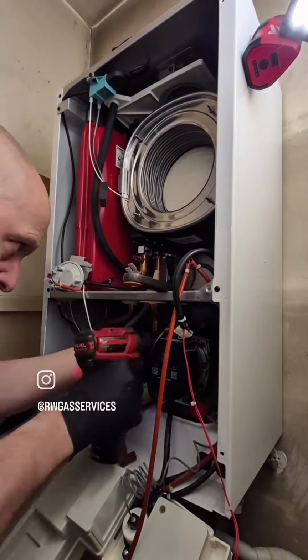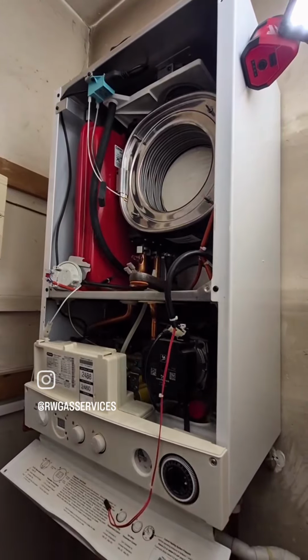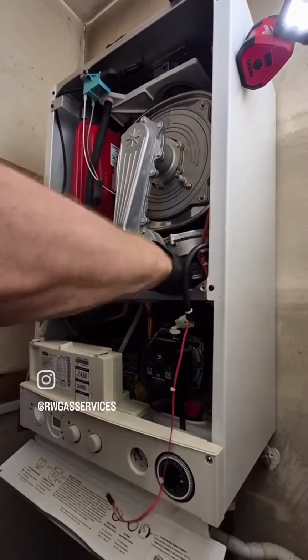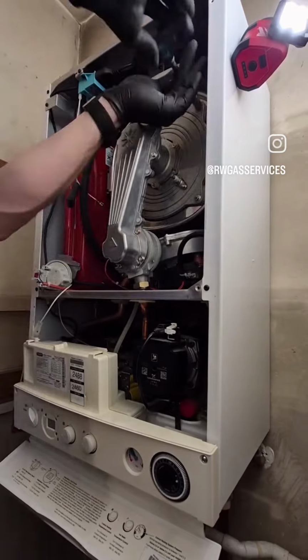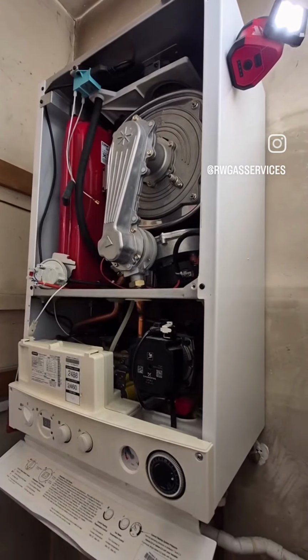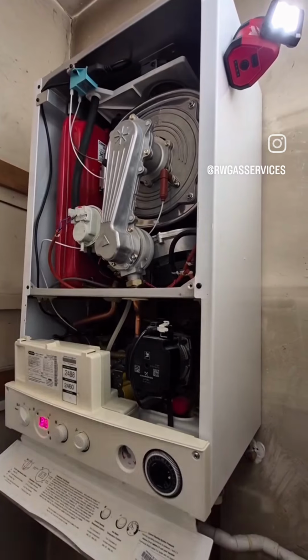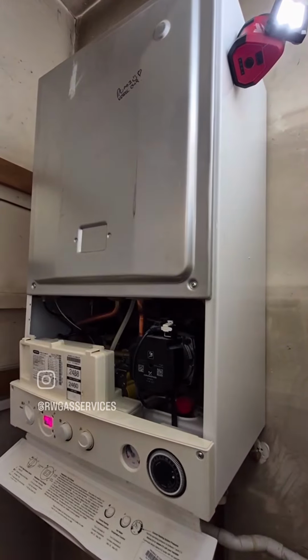Once I've done that and I've got it all filled back up, the burners are in, I need to be able to check certain gas connections with LDF, because after the gas valve tightness test, it won't show it. So I run it up on hot water and that burns off the film inside, burns off any grease before I analyse the boiler. I can then test the gas connections.